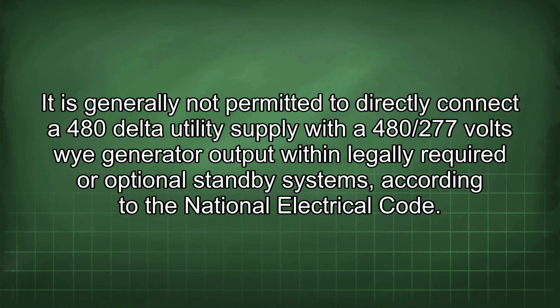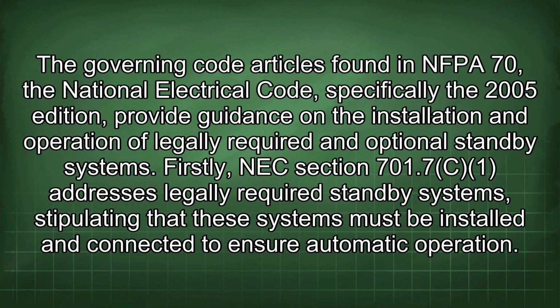It is generally not permitted to directly connect a 480 delta utility supply with a 480/277 volts Y generator output within legally required or optional standby systems according to the National Electrical Code. The governing code articles found in NFPA 70, the National Electrical Code, specifically the 2005 edition, provide guidance on the installation and operation of legally required and optional standby systems.